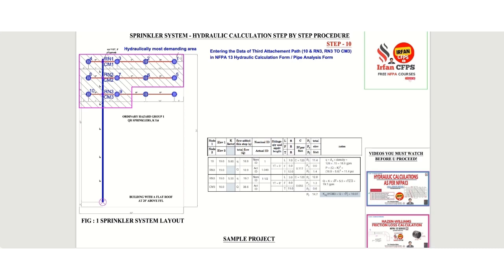As I already told you, the third attachment path is the path where water leaves the primary path at node CM3 and flows to 9 and 10th node. But the thing is here, there is a challenging point which you need to understand. The most challenging sprinkler between 9 and 10 is 10, to which we must deliver the water. So we choose to list the nodes for the path 10 to RN3, RN3 to CM3.